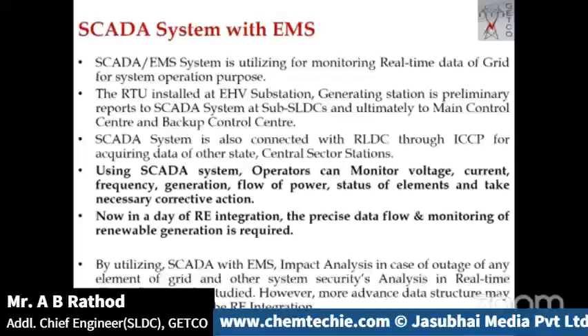SCADA system is also connected with RLDC through ICCP, acquiring data from other state and central sector stations. Using the SCADA system, operators can monitor voltage, current, frequency, generation, power flow, and status of elements, and take necessary corrective action.